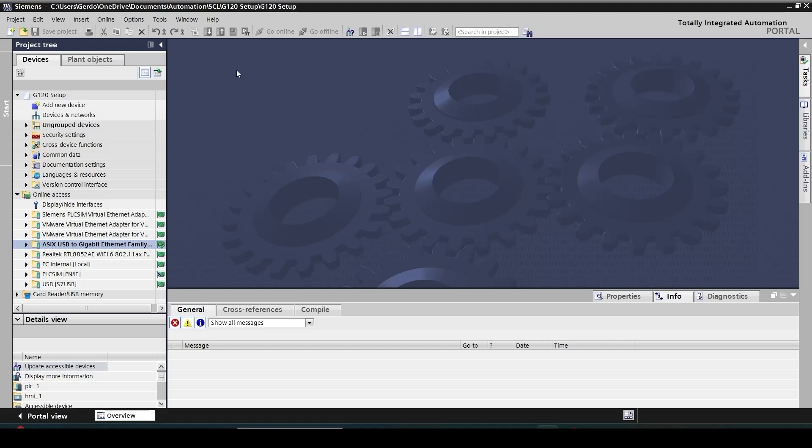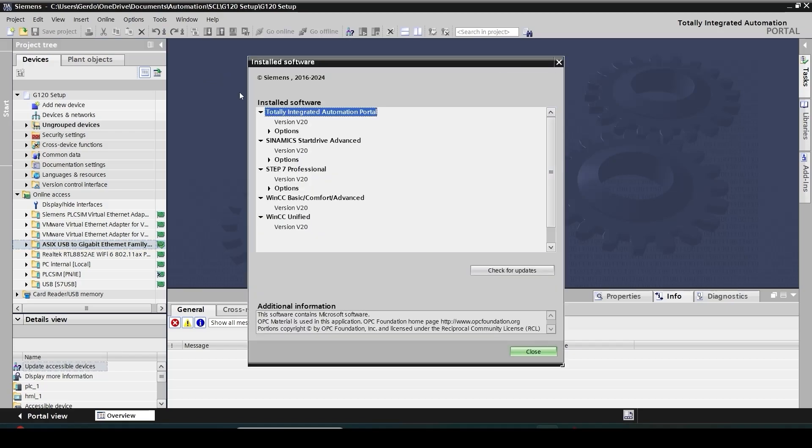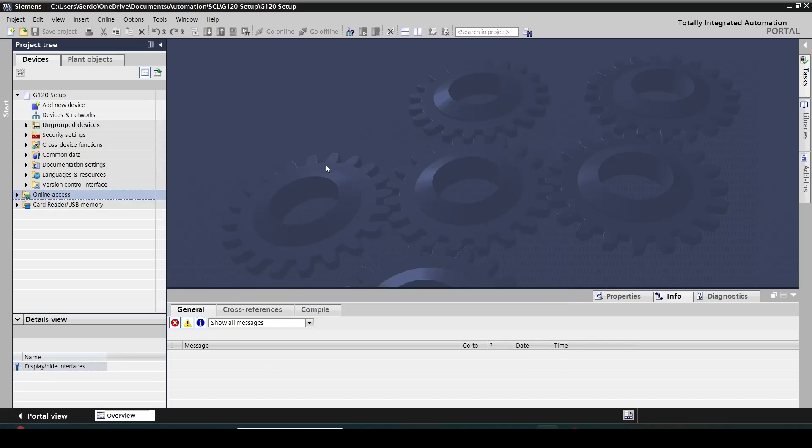Here I have my TIA portal open and I've already installed my Sinamics Startdrive. That's the tool you need for commissioning, configuration and testing the drive. You can check in your installed software if the Sinamics Startdrive has been installed. Right now my drive has been mounted and wired to my induction motor but it doesn't have any setting, and my PLC is connected to my drive via Ethernet port.